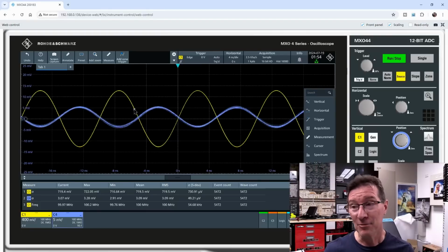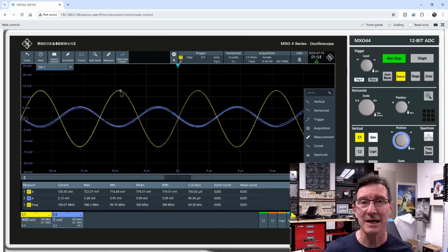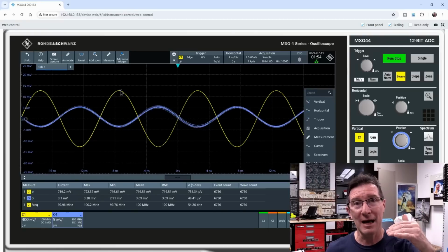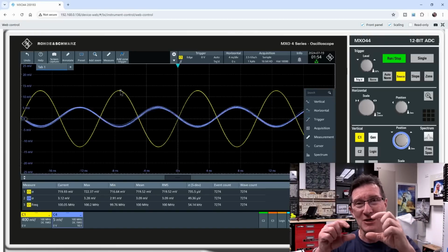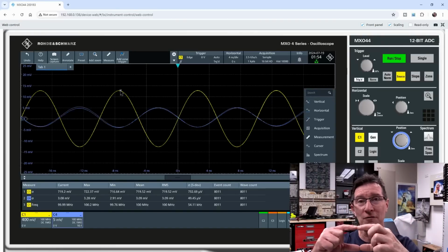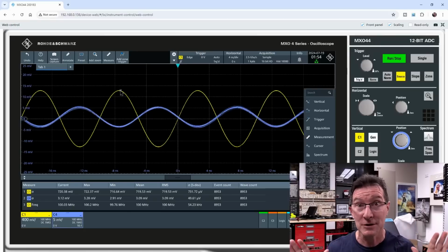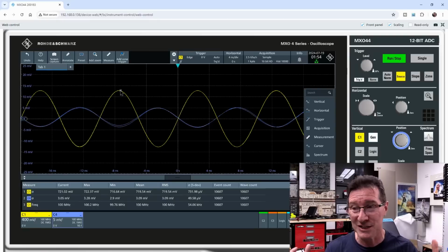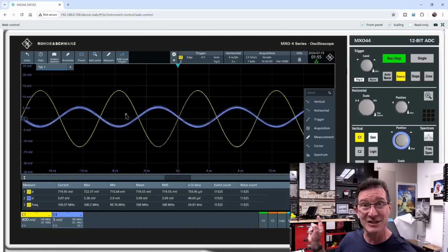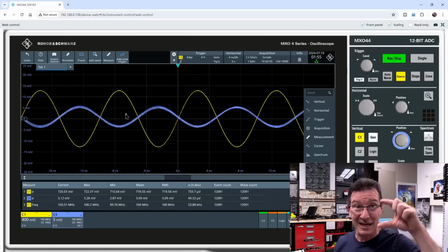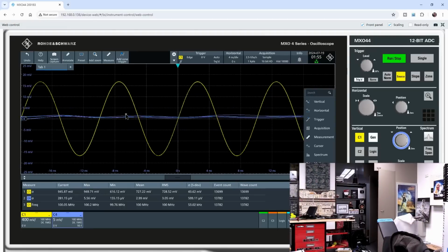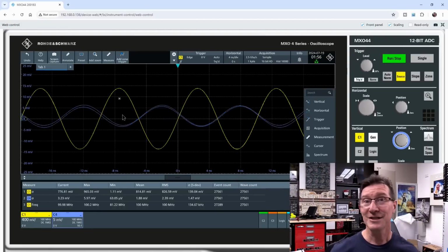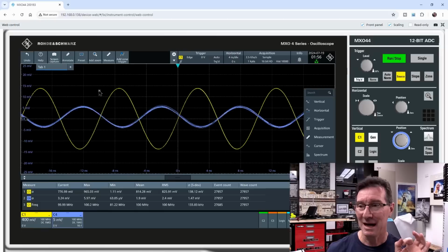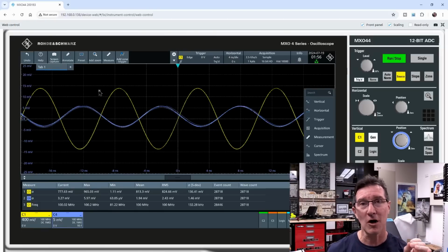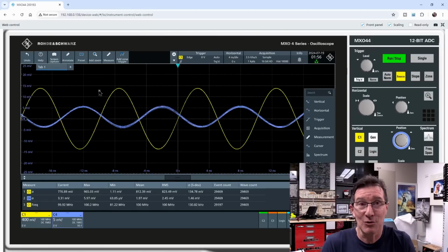Now you'll notice at 100 megahertz, our signal levels actually dropped here. It's not a problem from a measurement point of view, because what we're actually measuring at that particular point, the channel 1 input, is fine. So our measurements are correct, but our signal level has dropped because we do actually have some system capacitance there. So let me actually disconnect the cables, and you'll see the amplitude go up a bit. There you have it. I physically disconnected them. So that's interesting, huh? But as I said, it doesn't make a difference if the amplitude drops, as long as you're measuring it correctly at the channel 1 input, which we are.